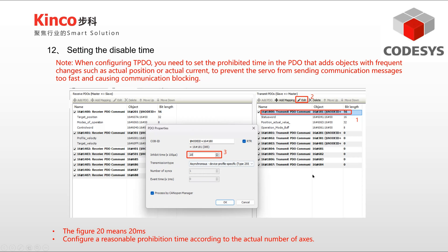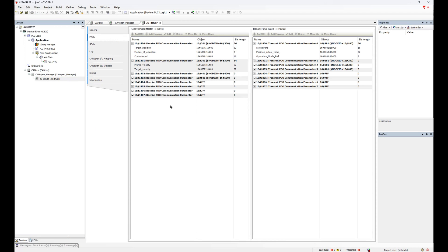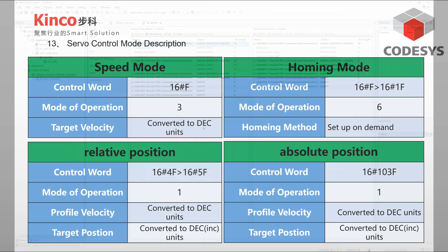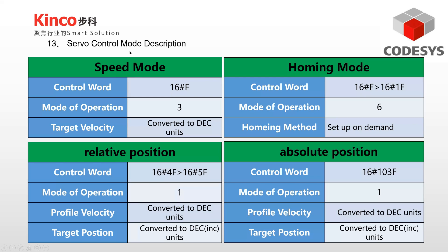When I set this to 20, it means that PDO data is sent every 20 milliseconds. Select a PDO list and select the communicate parameter address. The inhibit time needs to be set according to the actual number of axes. Then select the PDO transmission type. The above are the commonly used servo control modes and the corresponding parameters — you can set the parameters based on your control mode.